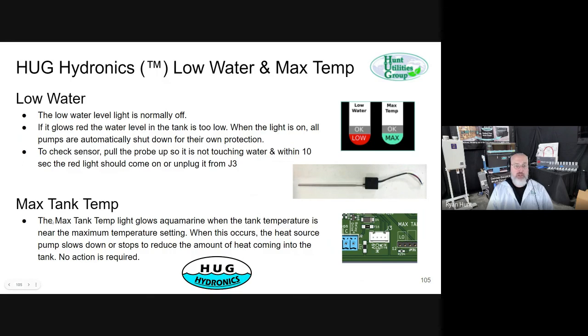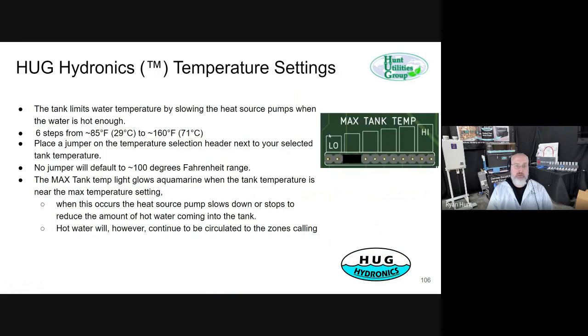The max tank temperature is a setting that we haven't talked about yet. We can set, with a series of jumpers, the maximum tank temperature that's allowed. The low here is about 85, high is about 160. It's not carefully calibrated, so we didn't put the actual specific numbers on there. We recommend somewhere right around the middle to start with, depending on what type of floor you have, just to make sure you're not sending heat to water that's too hot out there.